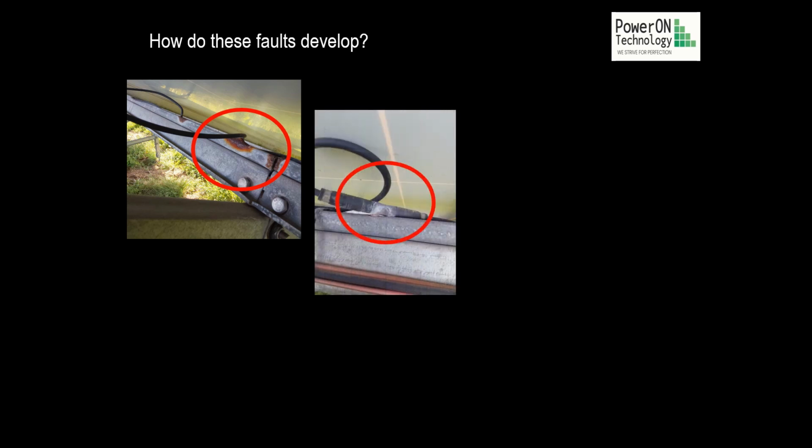And here are more examples of this. These are typical examples of a hidden fault, where first the one conductor shorts to ground and remains undetected, and then the second conductor shorts to ground, causing a direct short between positive and negative lines. The fuse protection is too slow to immediately clear this fault.